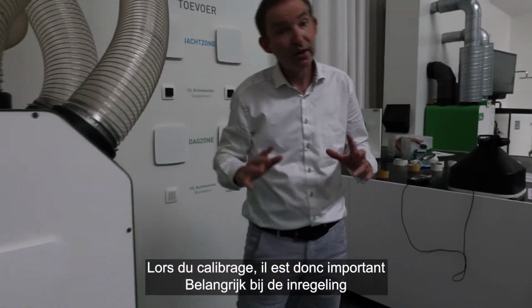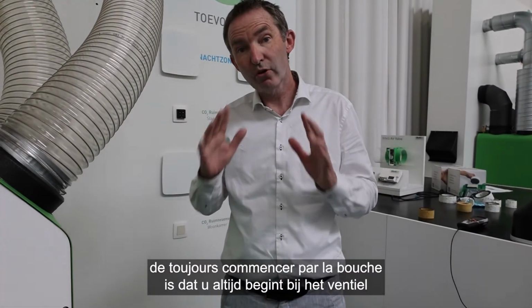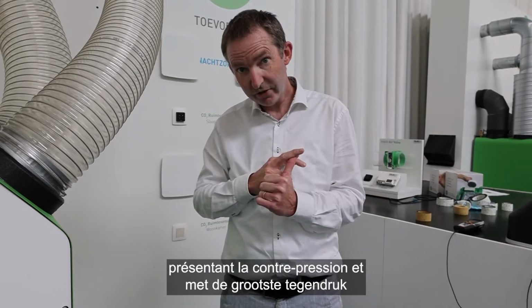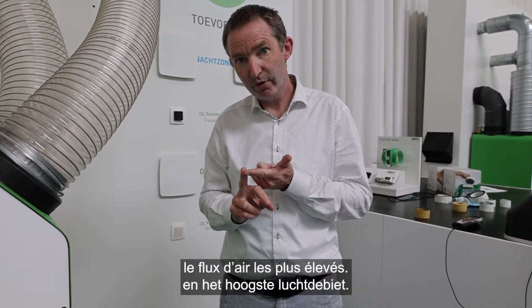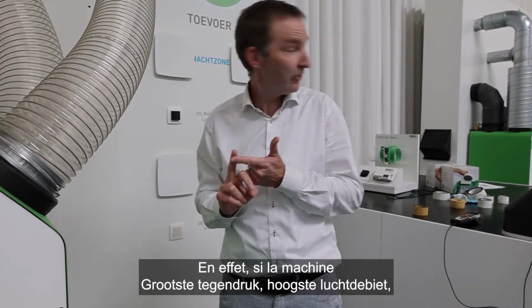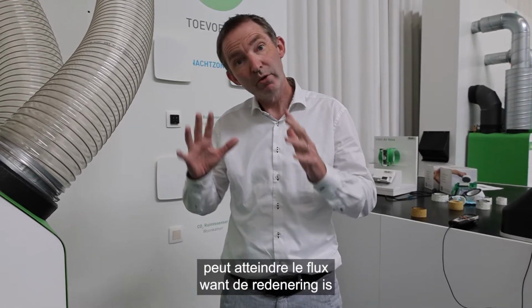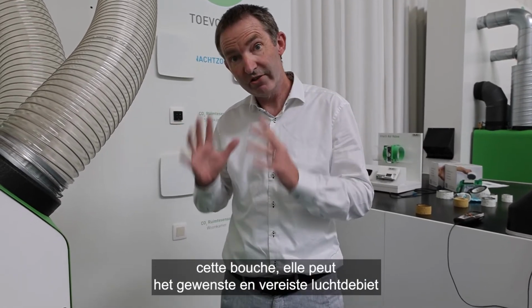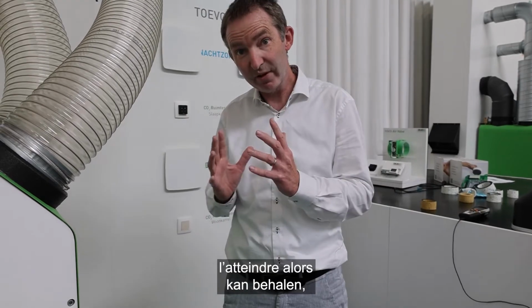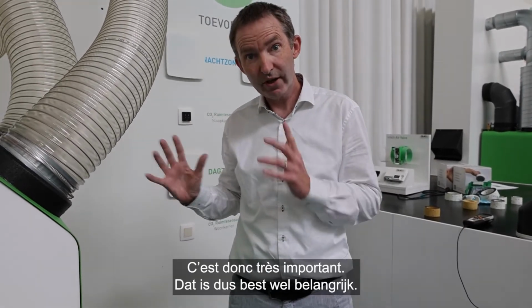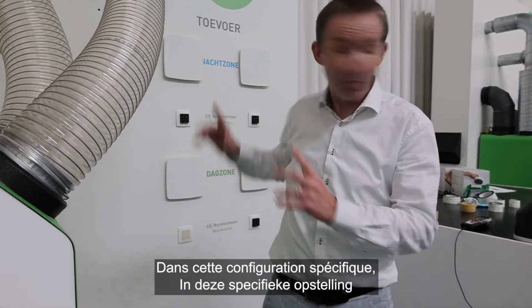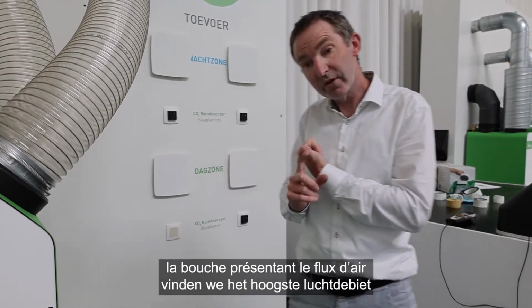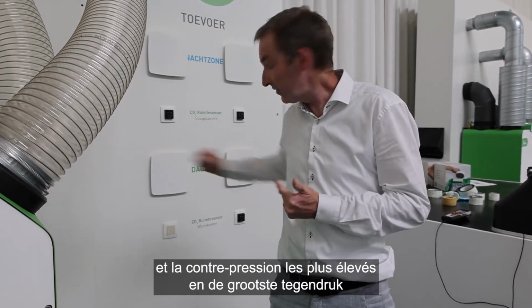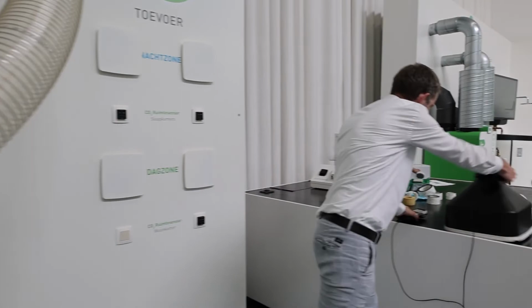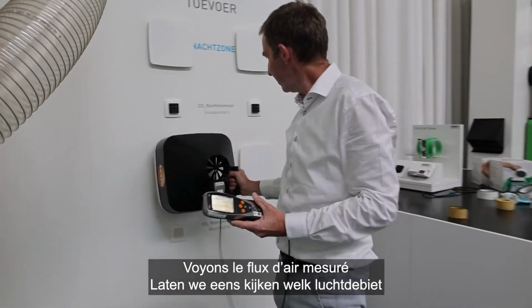So the important thing when calibrating is actually to start always with the vent with the highest counter pressure and the highest airflow. Okay, highest counter pressure, highest airflow. Because the reasoning is, when the machine can reach the desired and required airflow in that vent, it can reach it anywhere. So that's quite important. So in this particular setup, the vent with the highest airflow and the highest counter resistance is this one. So let's see how much airflow we have with our flow meter.